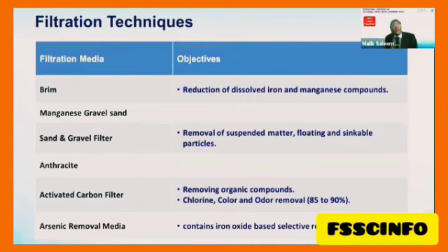Now, for selective ion removal, we have the Brim that reduces the iron and manganese compounds present in the water, and we have the sand and gravel filter that removes floating particles and suspended solids up to 40 micron. Then we have the anthracite activated carbon filter. These are their normal applications.